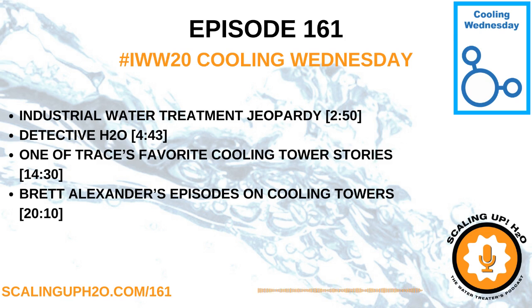That's the reagent doing its job just before it fades from the high sodium hypochlorite levels. Also, the total alkalinity test turned blue and yellow because of the sodium hypochlorite overfeed. The tracer test was affected as well, so I suspect you may be overfeeding your inhibitor product too. Lastly, that white foam we saw in the cooling tower water was, once again, from the sodium hypochlorite overfeed. That's why I turned off the oxidizing biocide pump.